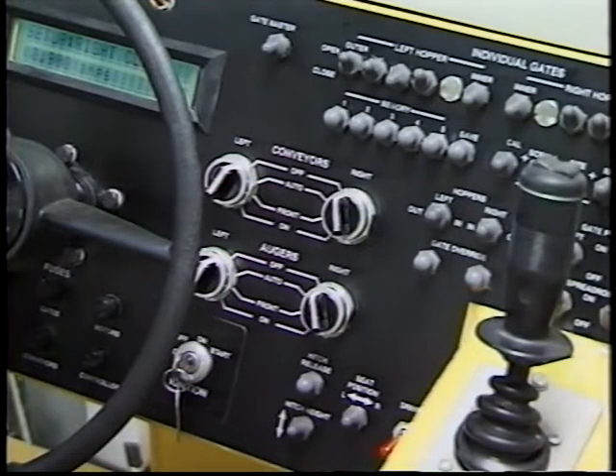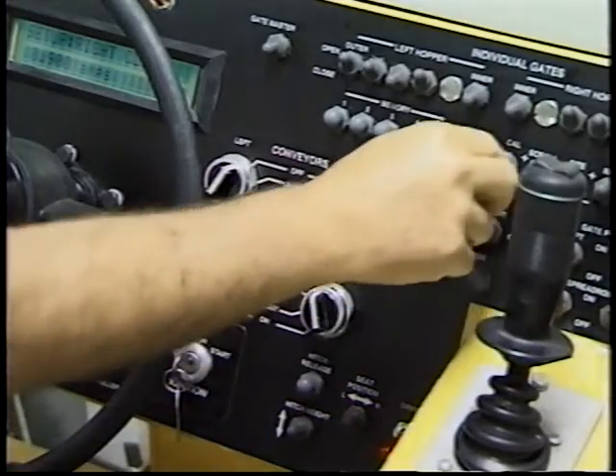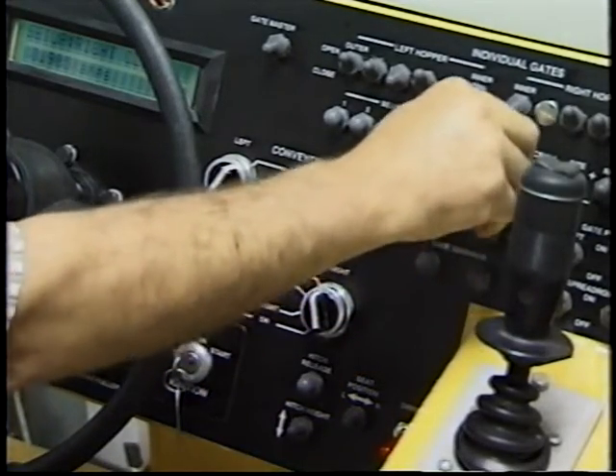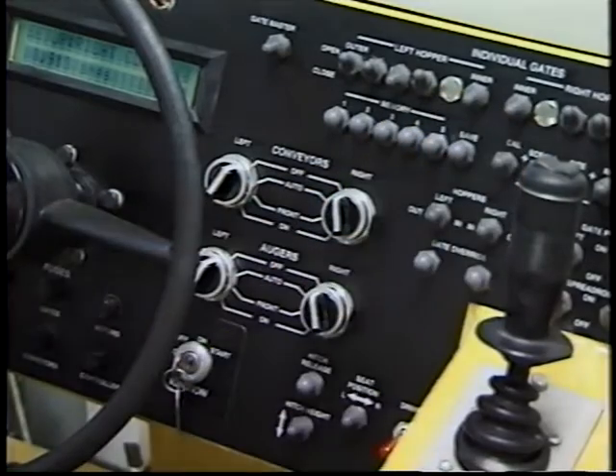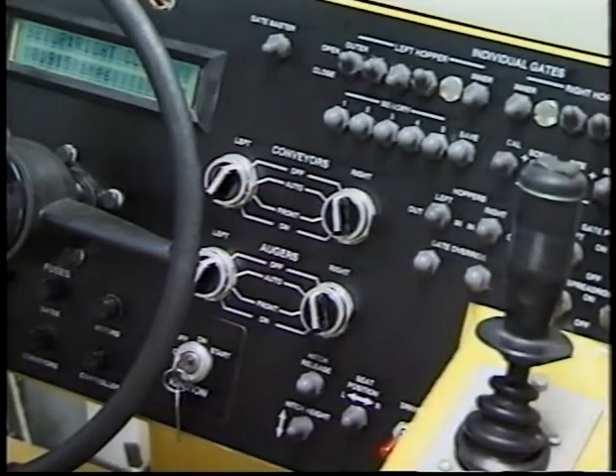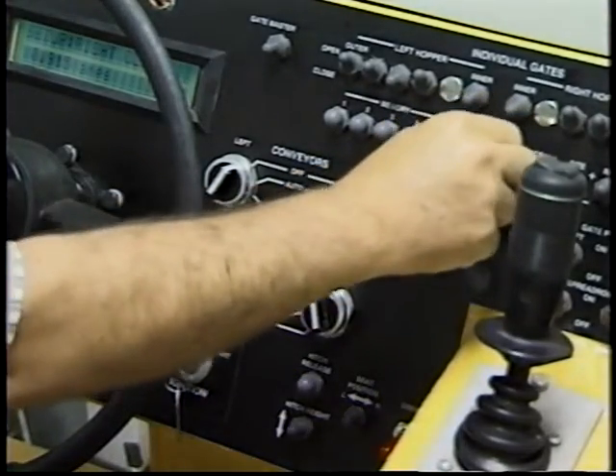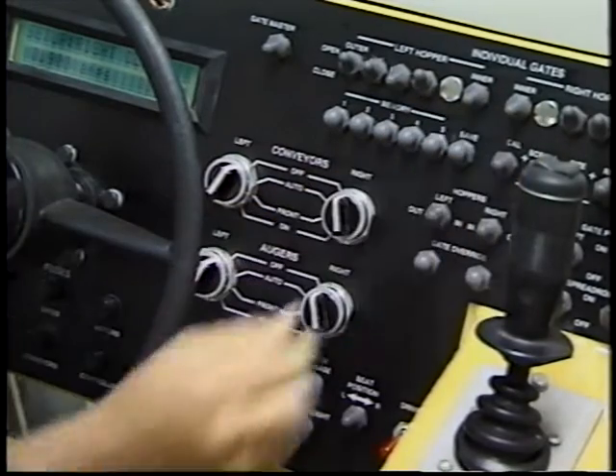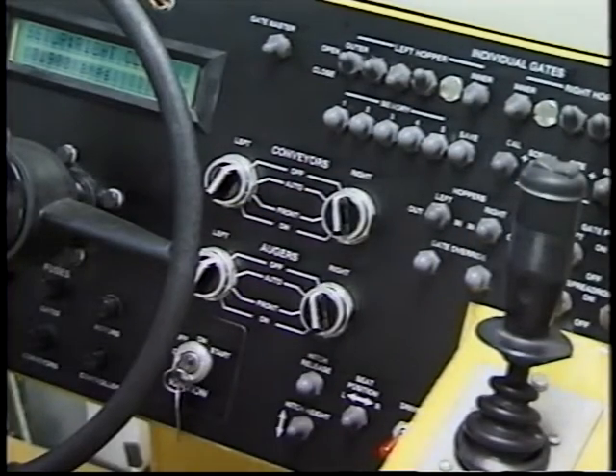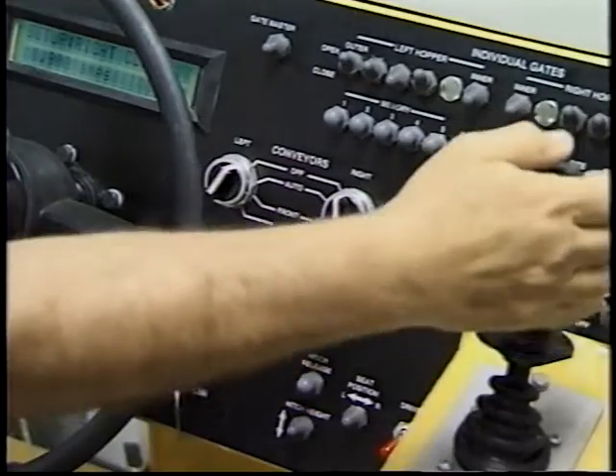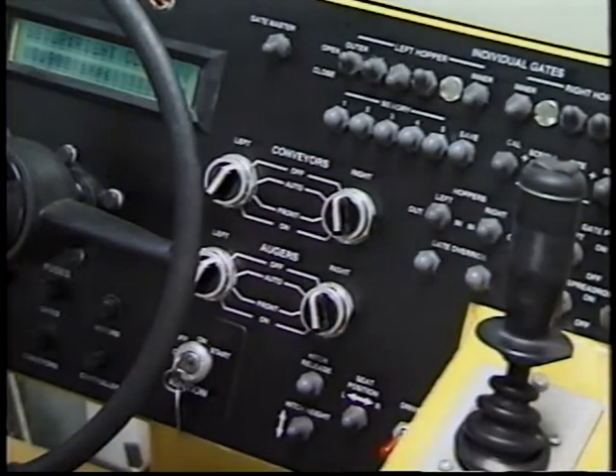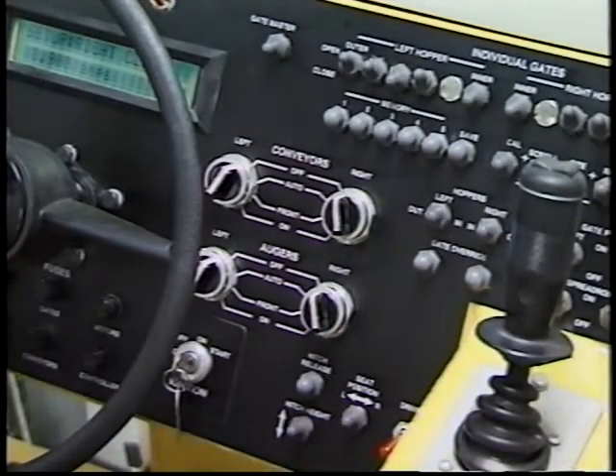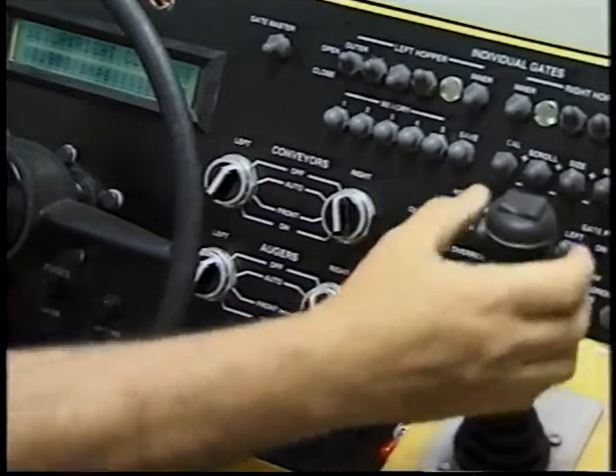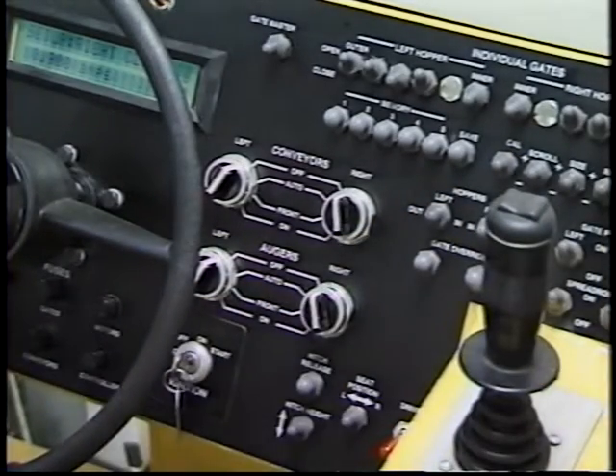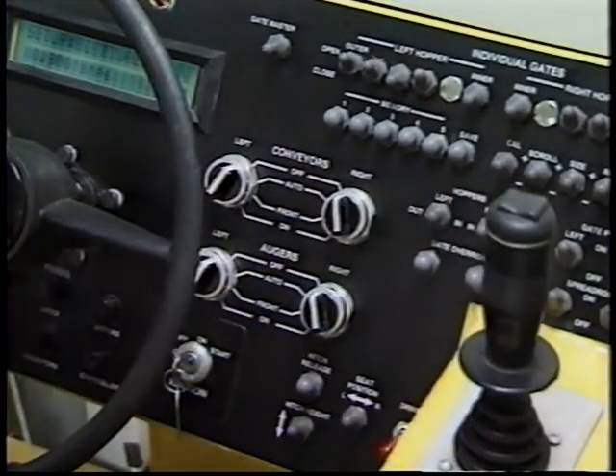Use the cal switch to toggle the current shown in this screen. Pushing the cal switch up will increase the current, thus increasing the speed of the gates moving from open to close, while pushing the cal switch down will decrease the current, thus decreasing the speed. Once any adjustments have been made, depress the left side of the rocker switch, closing the gate. Push the scroll switch down to move to the next screen.